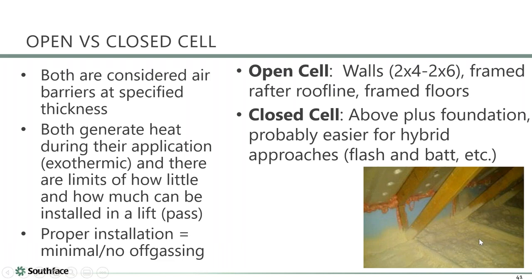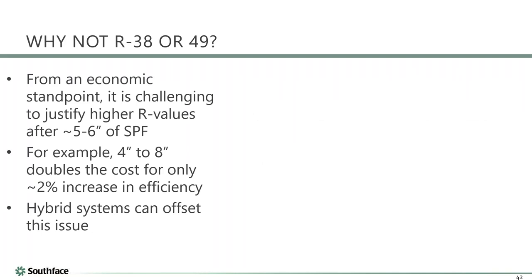This picture shows a flash-and-blow hybrid: they came in with roughly an inch of closed-cell foam on the flat ceiling, with well-detailed attic dams at the soffit and vent baffles. There's no ductwork in the space, so they'll come back and blow a whole lot of loose-fill insulation on top. It's a neat concept that squeezes the economics of spray foam to your advantage — you use just enough closed cell to get the air seal and condensation break, then fill the rest with cheaper insulation.